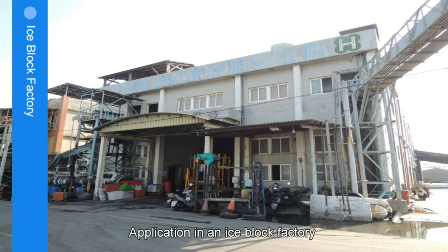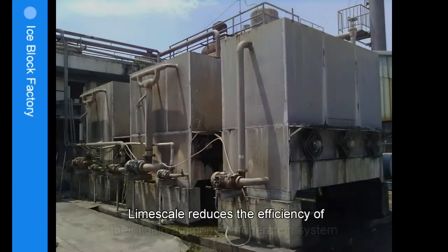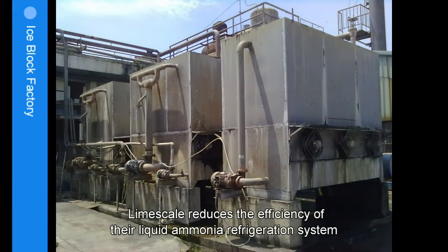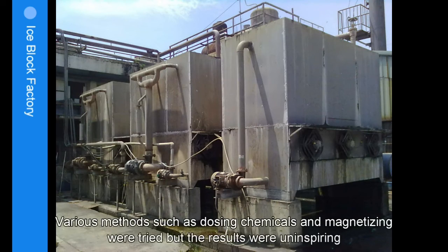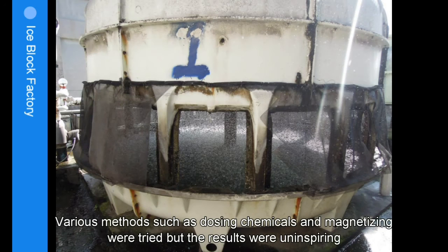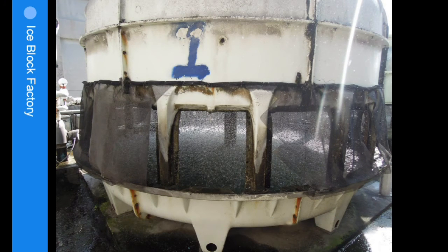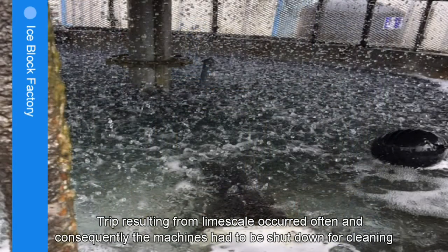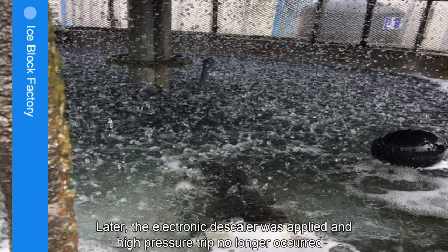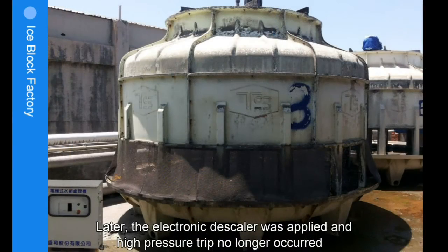Application in an ice block factory, mainly producing ice blocks. Limescale reduces the efficiency of their liquid ammonia refrigeration system. Various methods such as dosing chemicals and magnetizing were tried, but the results were uninspiring. Trip resulting from limescale occurred often, and consequently, the machines had to be shut down for cleaning. Later, the electronic descaler was applied, and high-pressure trip no longer occurred.